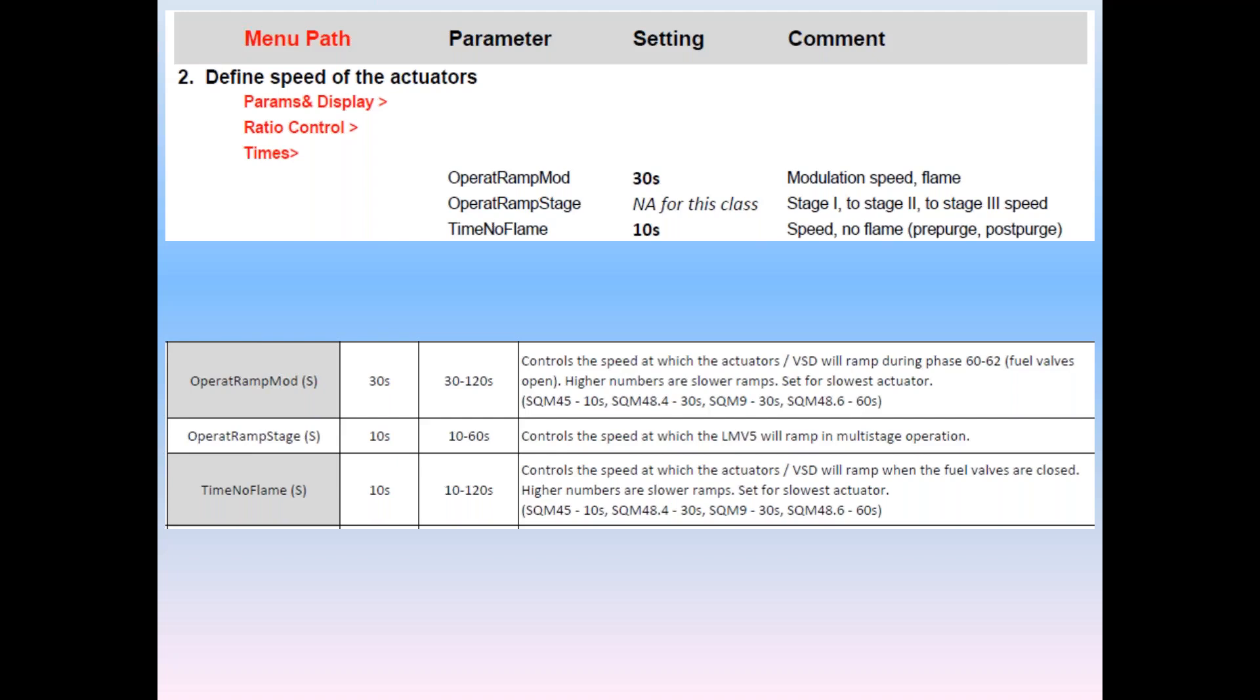Actuators can ramp through a range of speeds, some as low as 10 seconds. OperatRampMod parameter sets the speed of the modulation parameter until the flame is present. Time no flame sets the ramp speed when you do not have a flame, such as pre-purge and post-purge. The shaded boxes indicate parameters that most commonly used. OperatRampStage is for European-style burners that run oil stages, rarely used in the Americas.